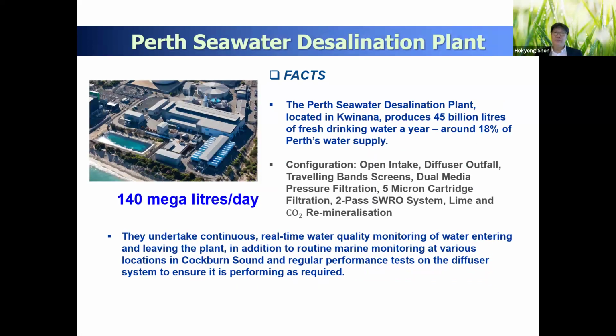The plant has an open intake, a diffuser, outfall, traveling band screen, dual media filtration, a 5-micron cartridge filter, 2-pass SWRO, lime, and CO2 remineralization.